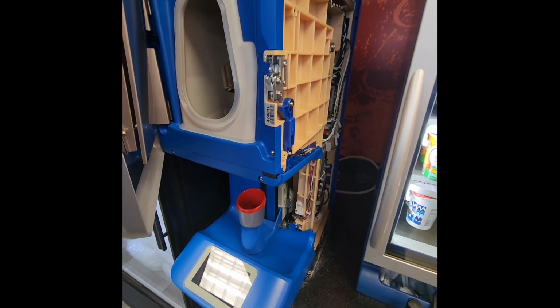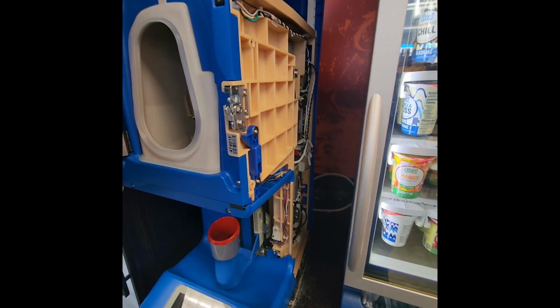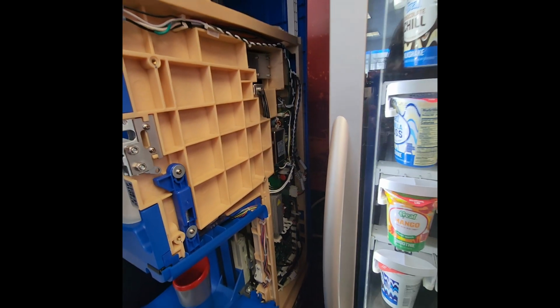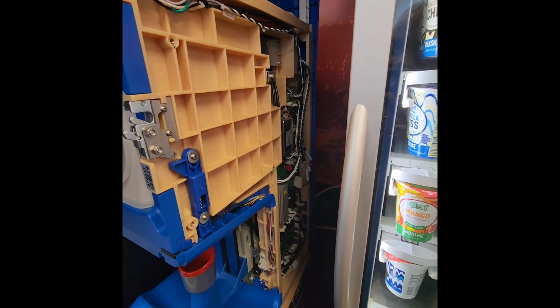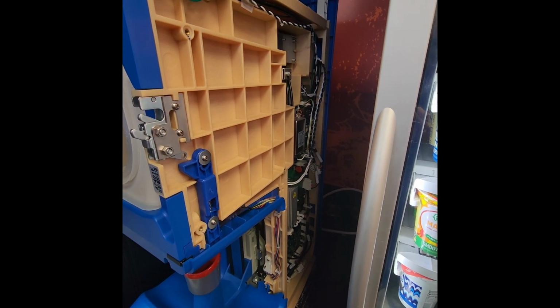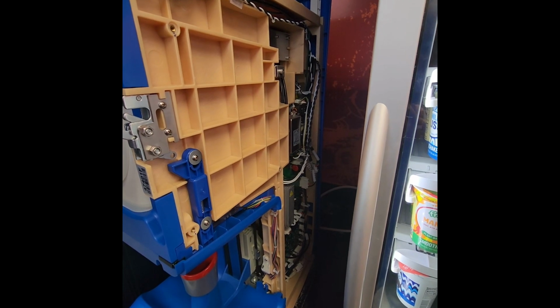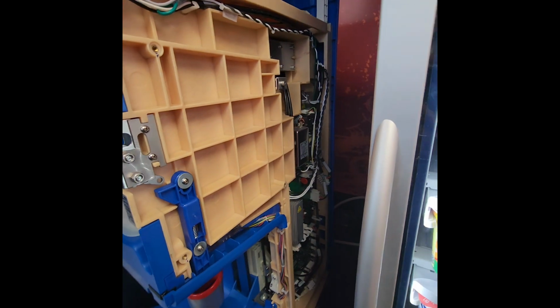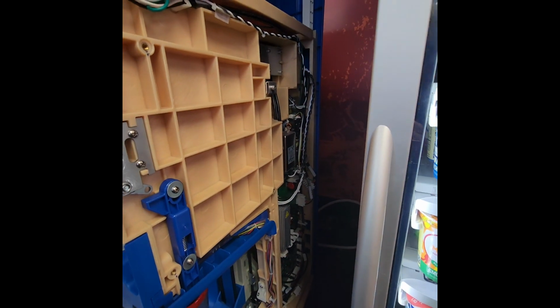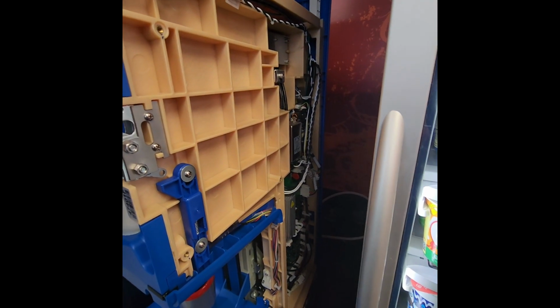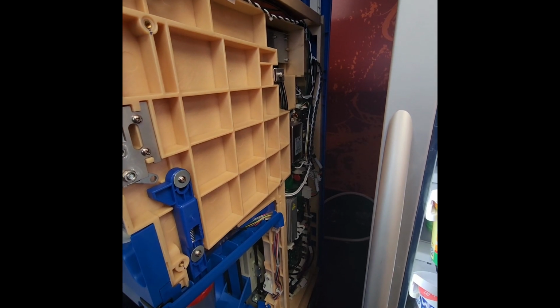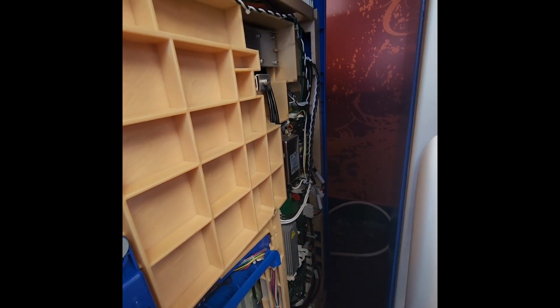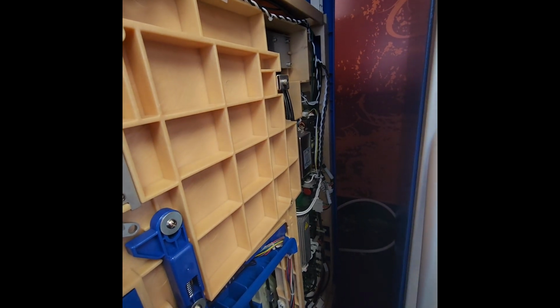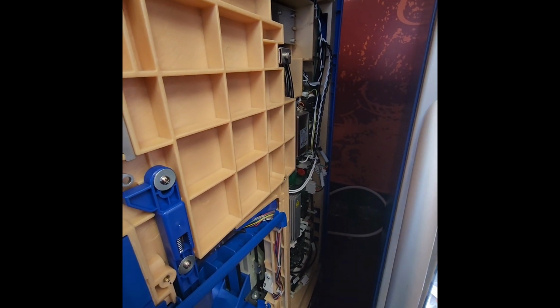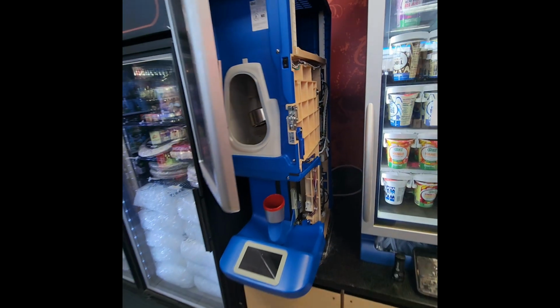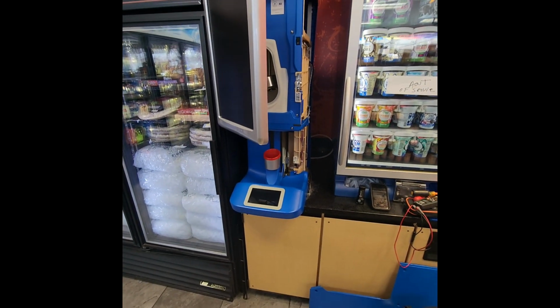I need to get access to the back panel to confirm whether it's the motor or the pump causing the short, because it could have a bad Procon pump that's stuck, creating a high amp draw that's tripping the breaker. So it could just be that, but I have to get access to the rear panel to reach that pump. It's a little crowded here, so I don't have much room to spin this around.